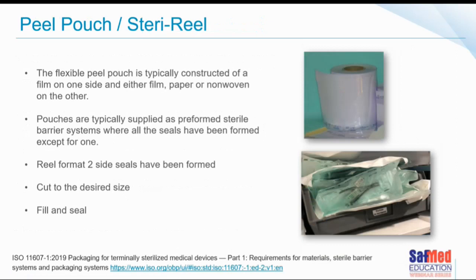A peel pouch or sterile reel is typically constructed of a film on one side and a paper or non-woven material on the other side. Pouches are supplied as pre-formed barriers where three of the seals have been formed, leaving one open. In reel format, two side seals have been formed — we then cut the reel to the desired length, fill the item, and seal the two ends.